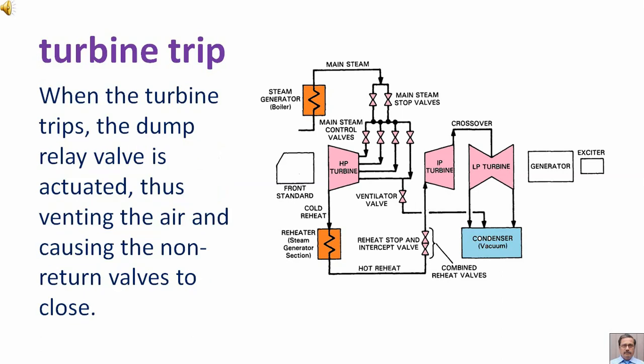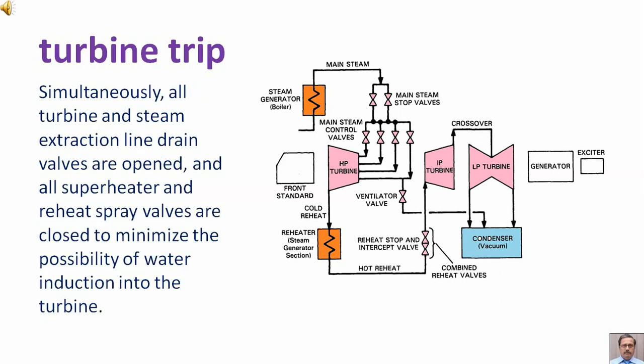When the turbine trips, the dump relay valve is actuated, venting the air and causing the non-return valves to close simultaneously. All turbine and steam extraction line drain valves are opened, and all superheater and reheat spray valves are closed to minimize the possibility of water induction into the turbine.